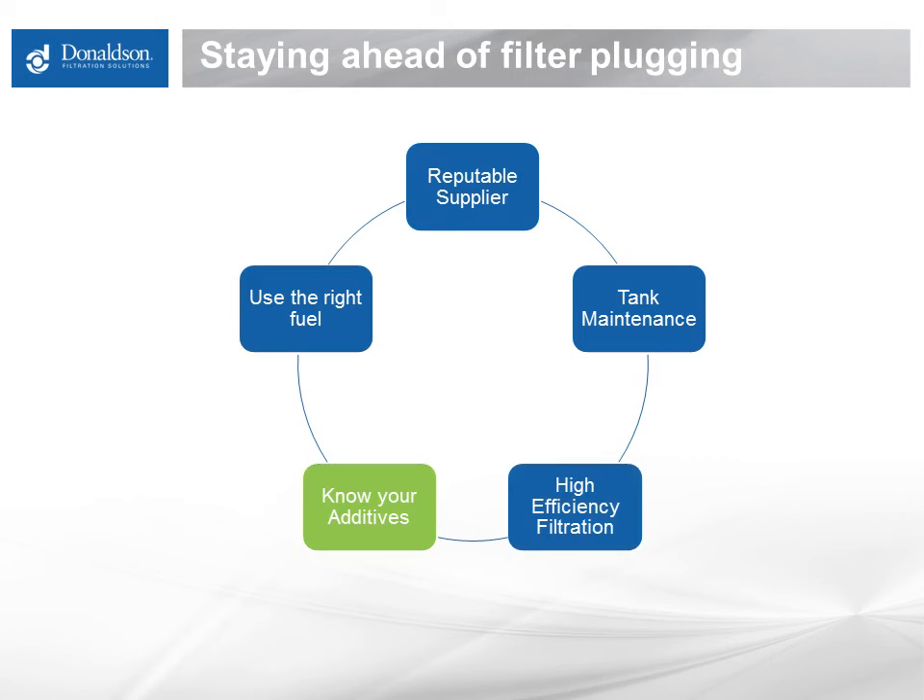Know what you are fixing with additives at the end user site. Virtually all fuel delivered meets industry minimum specifications. Adding more fuel additives to what is already there may or may not be necessary — the fuel property of concern may have been fine in the first place. Some additives to proactively manage a current or previous microbial issue, or added stability improver for long-term storage of fuel, can do some good, and many equipment manufacturers recommend detergents. But for some others it is critical to know what the fuel property is you are trying to fix and why — it is common to fall back to the 'more is better' approach, and in some cases that can be disastrous when it comes to filterability. Lastly, buy fuel appropriate for the weather conditions. It is tempting to save money by purchasing fuel that someone claims will work at or below the fuel's natural cloud point, or that has a lower pour point or cold filter plugging point than normal, but if these conditions occur, operational issues tend to arise.